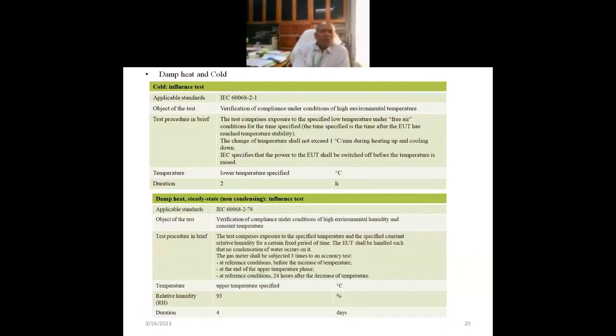In cold influence test, the applicable standard is IEC 60068-2-1 and object of test is verification of compliance under conditions of low environmental temperature. The test procedure in brief is the test comprises of exposure to the specified low temperature under free air conditions for the time specified. That means the time specified is the time after the EUT has reached temperature stability. The change of temperature shall not exceed 1 degree per minute during the heating up and cooling down. IEC specifies the power to the EUT shall be switched off before the temperature rise. Duration is 2 hours.